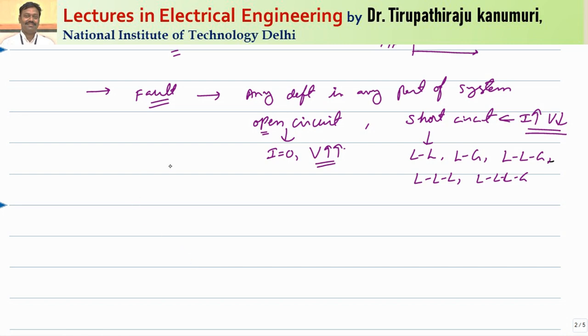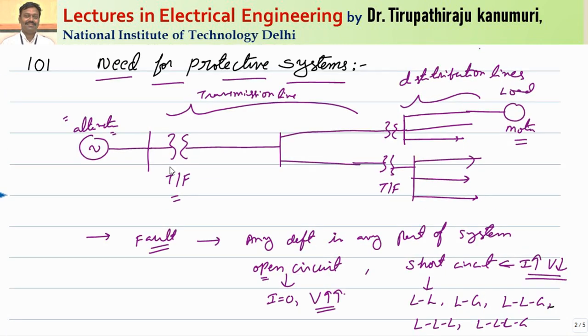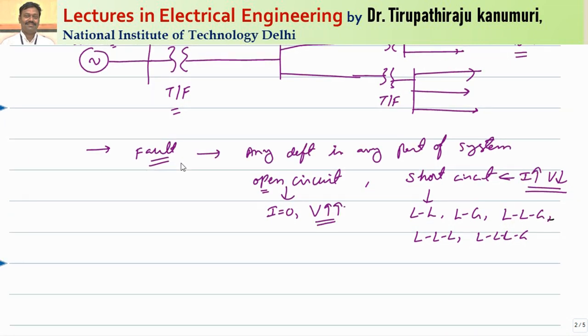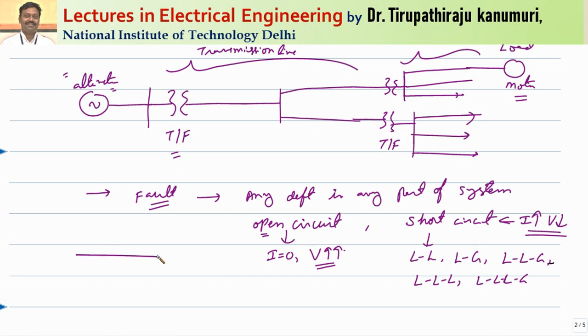This fault can happen on any one of these systems. Let us briefly discuss different types of faults that can happen. Taking the transmission line — it basically consists of three conductors and each conductor has insulation. In the overhead transmission line, conductors are connected to an insulator through a cross arm. The fault can happen between a conductor and the cross arm, since the cross arm is at ground potential — a short circuit or flashover can happen.